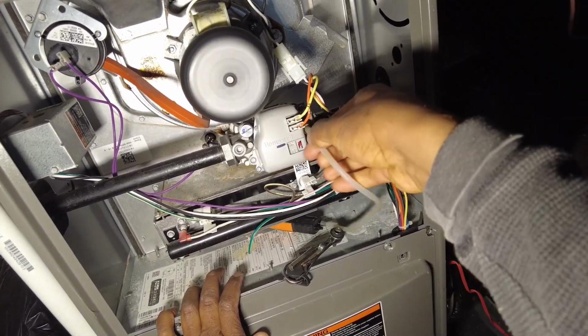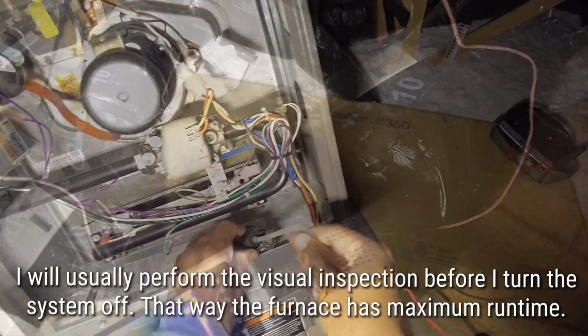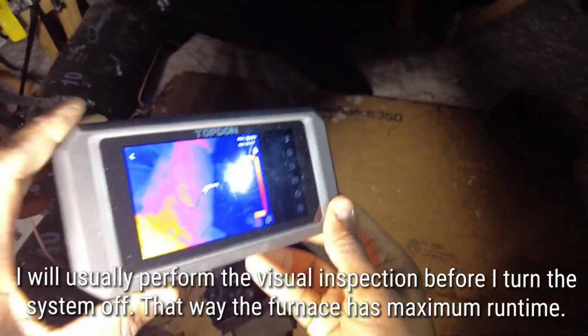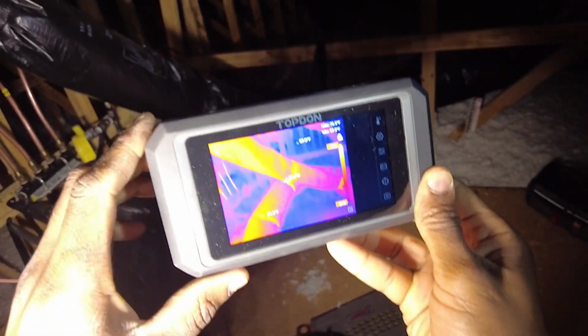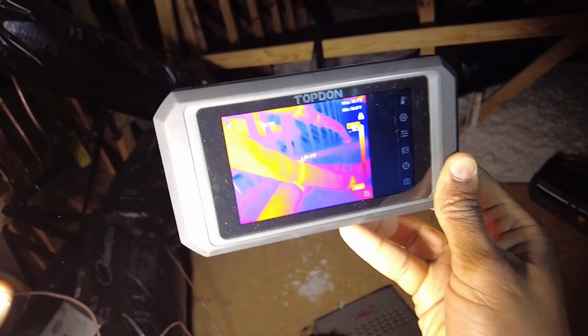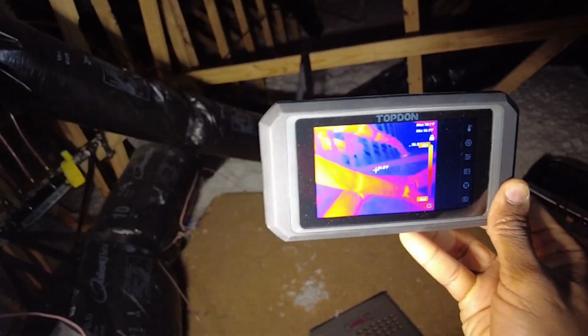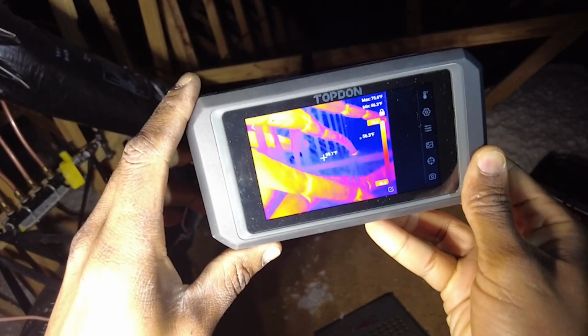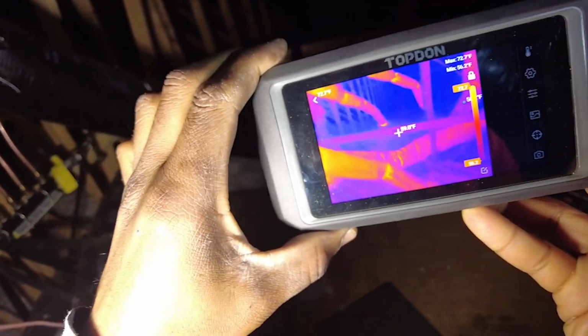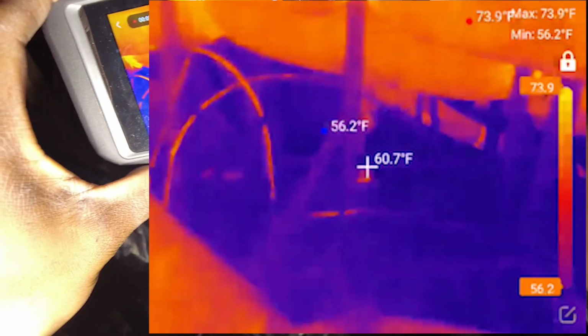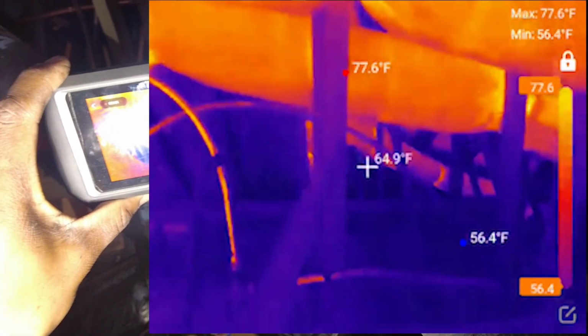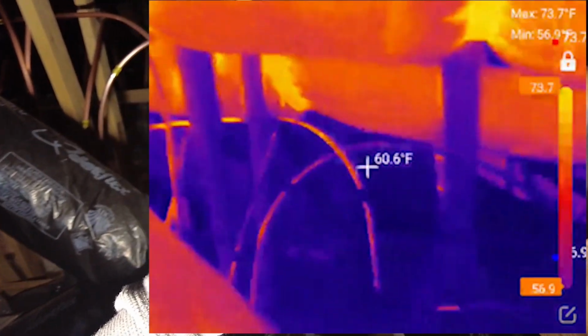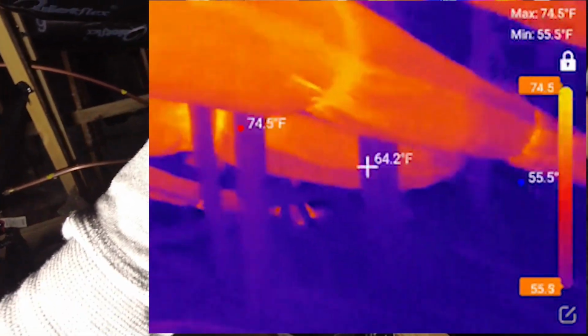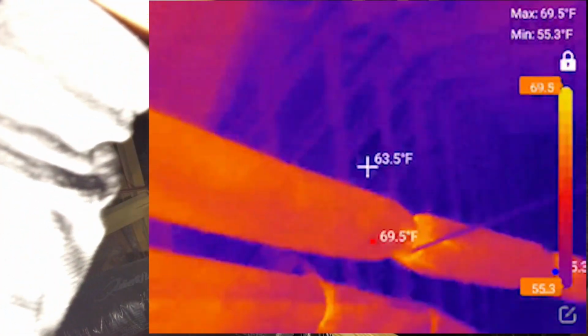Now it's going to be a lot of visual inspection, you know. Okay, so yeah. So basically with the thermal imager, what I'm trying to do here is I'm using it to inspect the ductwork, do like a really rough inspection. And as long as you see the heat's contained within the ductwork, you don't see the heat spread out all into the attic and stuff like that, 9 times out of 10 there's not going to be any large cracks or anything like that. All right, so we're not seeing any crazy spread out hot zones. Everything seems to be pretty well contained in the duct, right? But yeah, this is a pretty slick image, just the TOPDON.